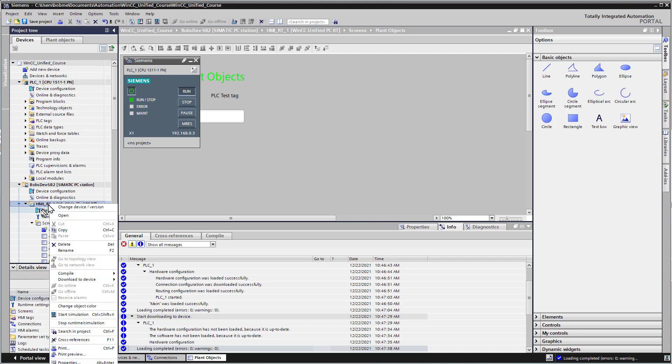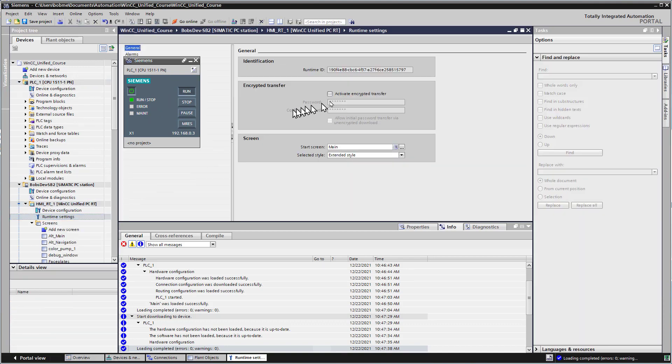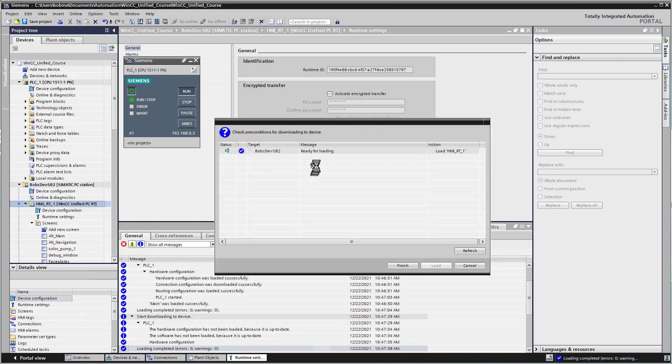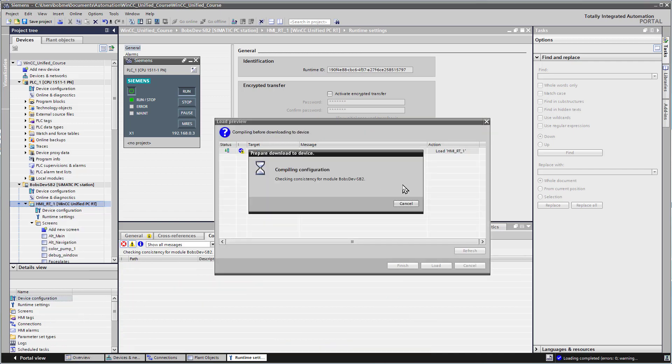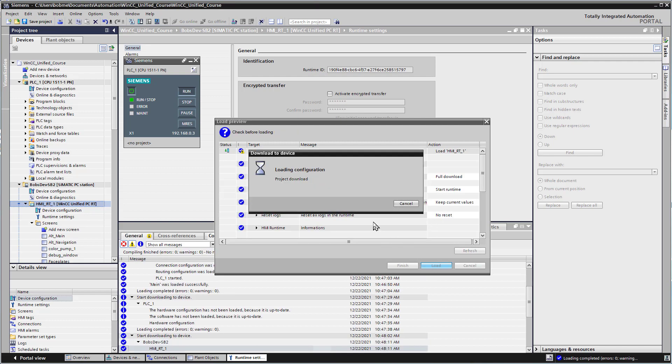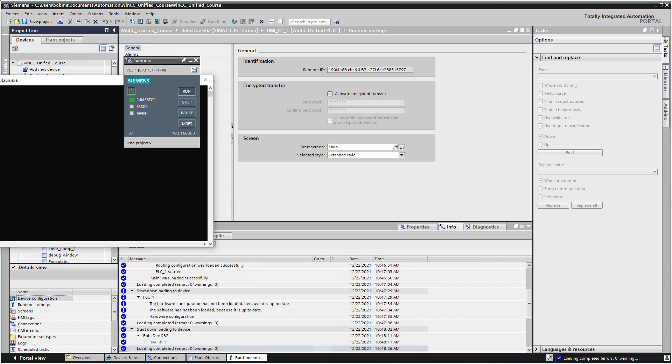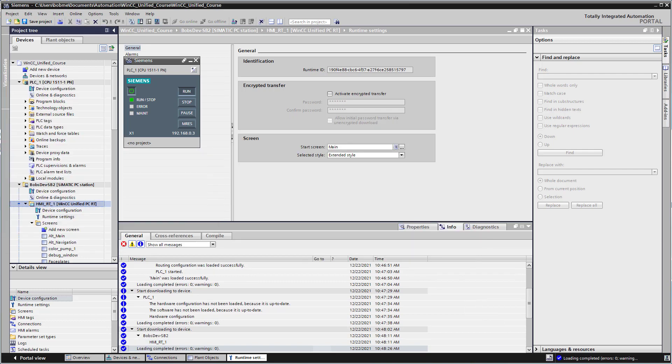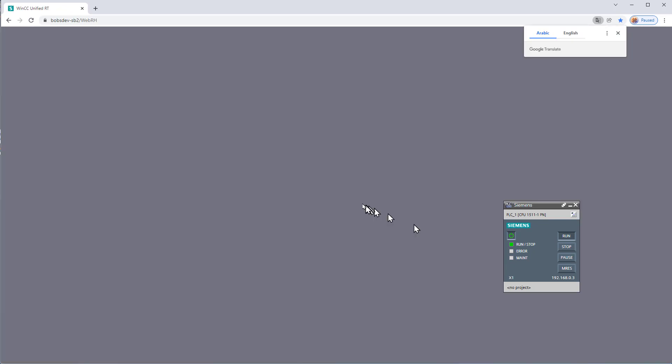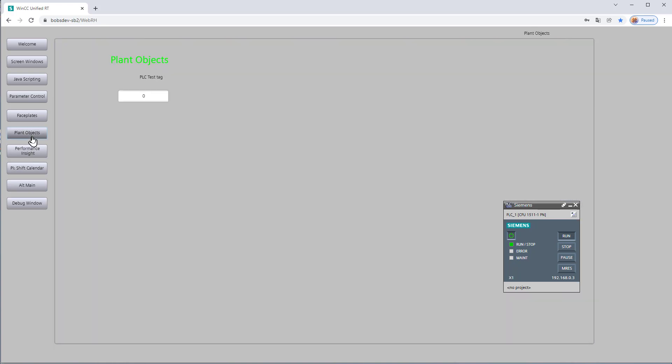We're going to go to our runtime device, and under runtime settings, uncheck encrypted transfer because you can't use that if you're doing simulation. Then we'll right click and do start simulation. We'll leave these at default and click load. Then we can pull up our browser and go to our runtime. If we go to plant objects, we don't have a grayed out field, and that's pretty good.